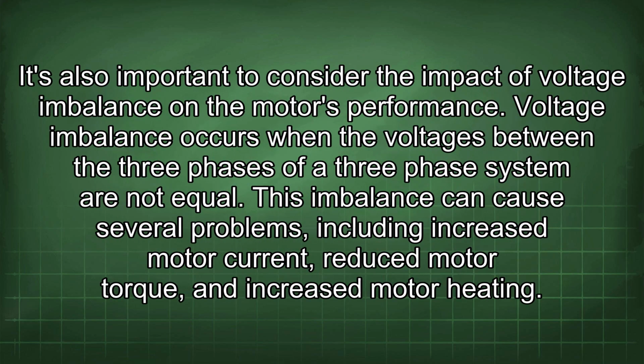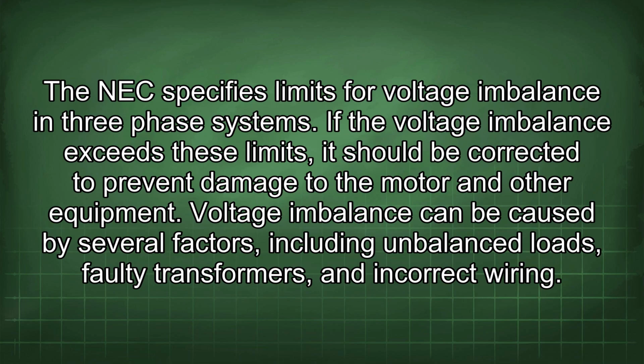It's also important to consider the impact of voltage imbalance on the motor's performance. Voltage imbalance occurs when the voltages between the three phases of a three-phase system are not equal. This imbalance can cause several problems, including increased motor current, reduced motor torque, and increased motor heating. The NEC specifies limits for voltage imbalance in three-phase systems. If the voltage imbalance exceeds these limits, it should be corrected to prevent damage to the motor and other equipment.